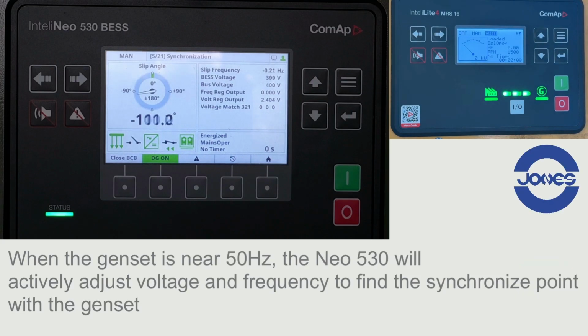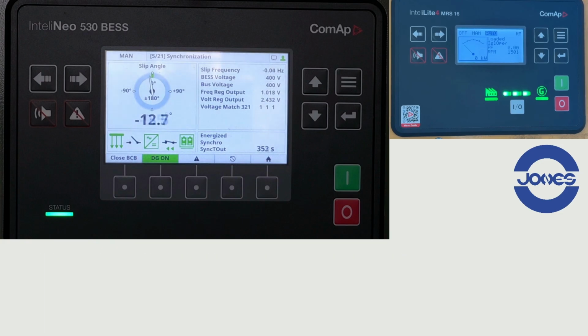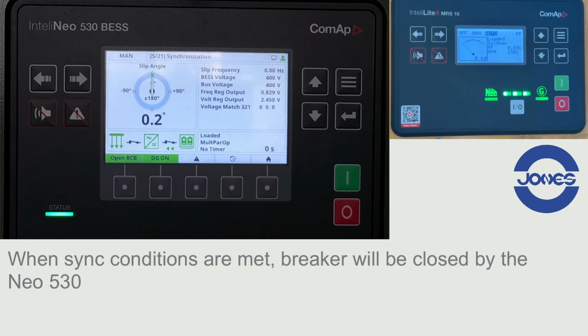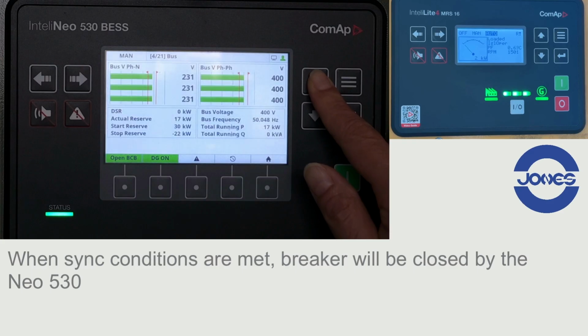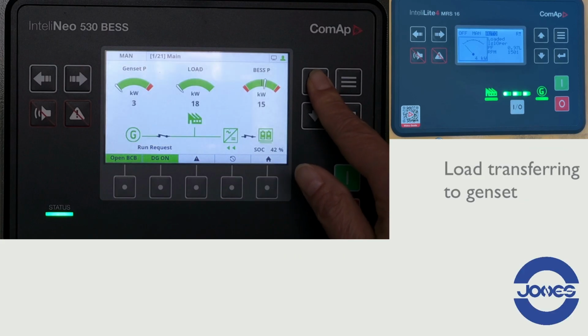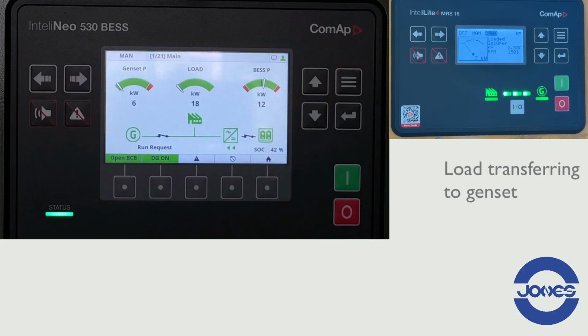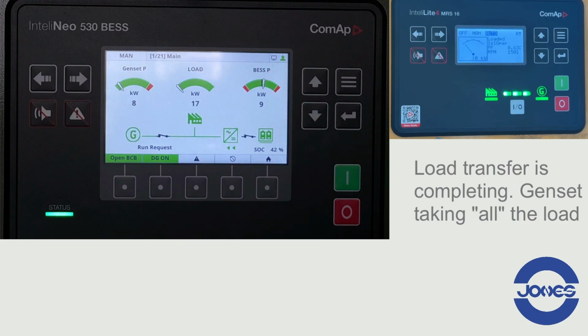When the genset is near 50 Hz, the Neo 530 will actively adjust voltage and frequency to find the synchronous point with the genset. When sync conditions are met, breaker will be closed by the Neo 530. Load transfer is completing, genset is taking all the load.